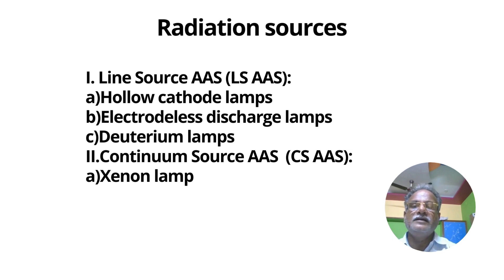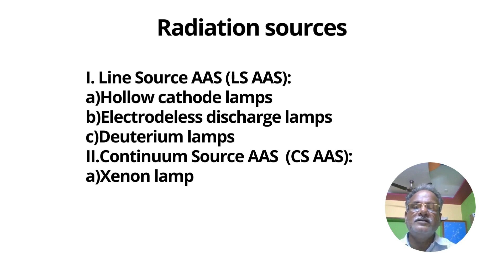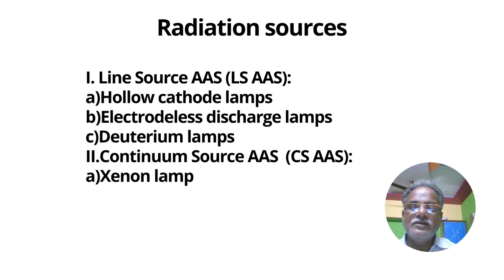Radiation sources. Line-source atomic absorption spectroscopy and continuum-source atomic absorption spectroscopy can be classified based on their radiation sources. Usually, hollow cathode lamps and electrodeless discharge lamps and deuterium lamps are used for line-source AAS. For continuum-source atomic absorption spectroscopy, xenon lamps are widely used.